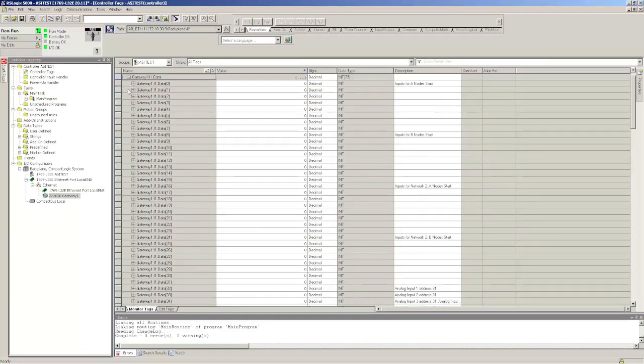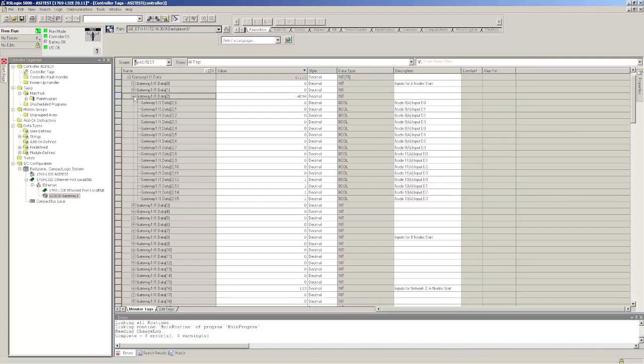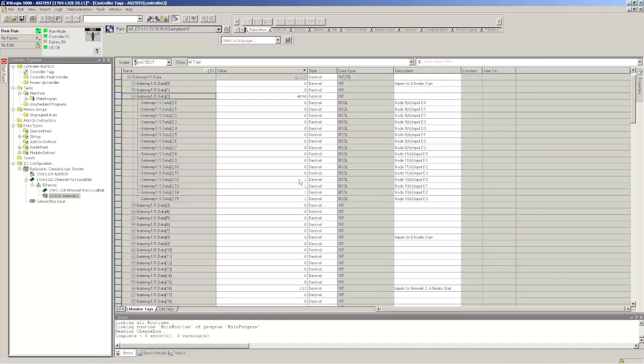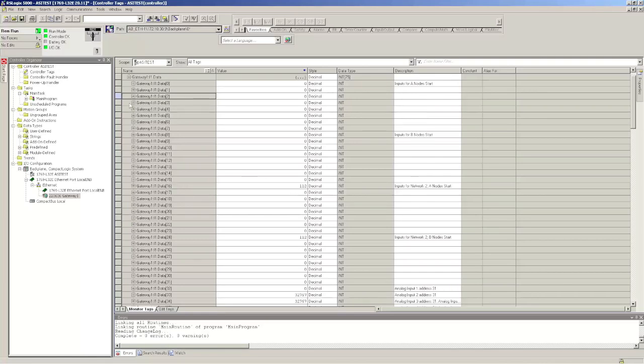If I go to my I.O. table, for example, my input data, I'm going to show you Node 10, for example. That's my e-stop. My e-stop is released right now because here's Node 10. All the bits for Node 10 are on: 1, 1, 1, 1. When I go ahead and press the e-stop, all the inputs go off at 0. That's all it takes. Get everything running.